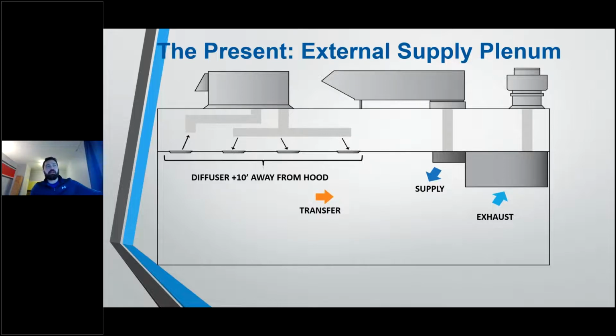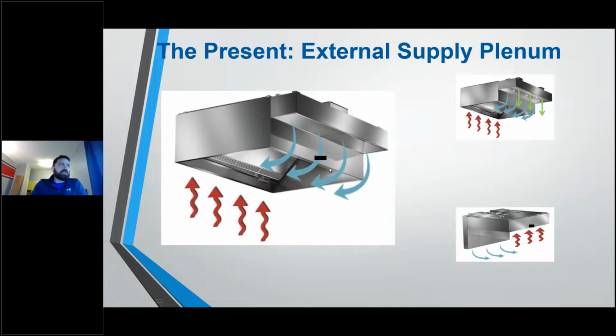And then the rest of that transfer air is going to be made up with your rooftop air or any mechanical or gravity transfer, typically 20% transfer into a kitchen with the idea of keeping the kitchen slightly negative so you don't have smells escaping. Now, when you do these dedicated makeup air fans, you're typically going to have this image on the left.